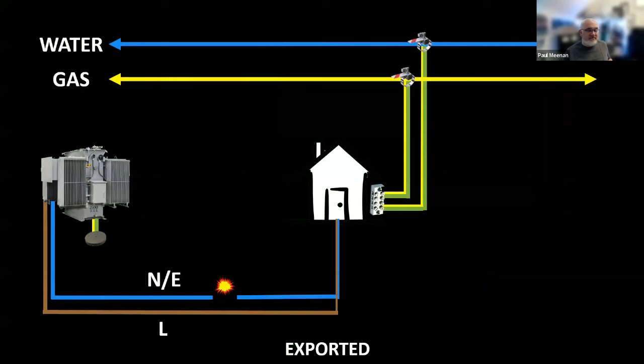On a single house, much easier in the countryside, with combined neutral earth, if you fail on the connection, then your neutral earth return has only one way to go, and that's straight down to ground. Henceforth, we're recommending local electrodes now as well. So that's known as exported diverted neutral current.